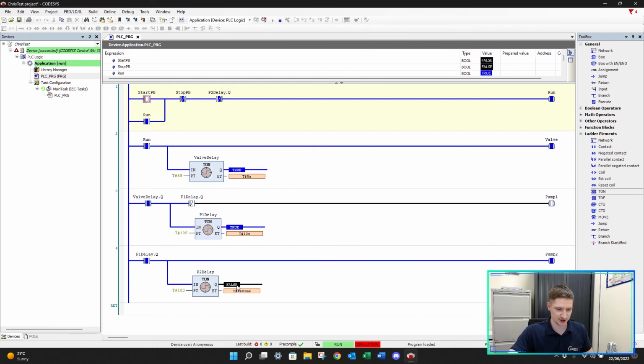And if we watch this, you might see us turn on just a blip. And that just proves it does turn on. So just keep your eye on it. No, it was too quick. It's only on for one PLC scan. Every now and then you might see it just turn on, and that's just the laptop updating at the same time as the scan of this program here. But it did turn on, and it must have turned on because that had opened, turned off our run, and reset our entire process from there.